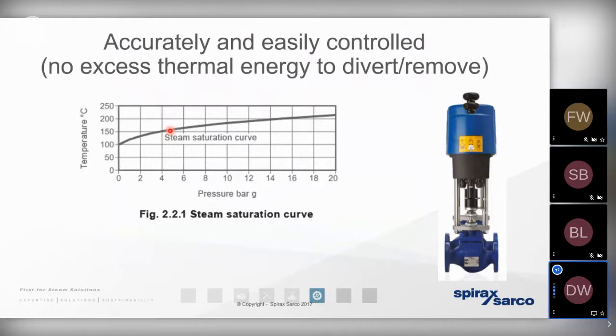Whereas if you compare that with a water-to-water heat exchanger, well, we need a three-port valve, and we'd need that for two different reasons. First of all, steam gives up its heat energy by condensing. So the heat exchanger will only call for and condense the amount of heat that the process requires and no more. But because of that pressure temperature relationship, it also means that it's even easier to control.